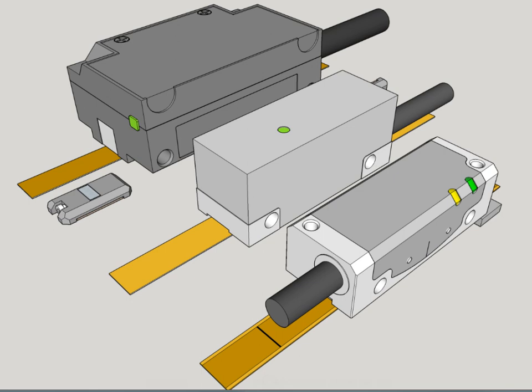When specifying an optical encoder, it's important that the encoder have extra protection built in to prevent contamination from dust, vibration, and other conditions common to industrial environments. Optical incremental scale periods vary from hundreds of micrometers down to sub-micrometer. Interpolation can provide resolutions as fine as a nanometer.